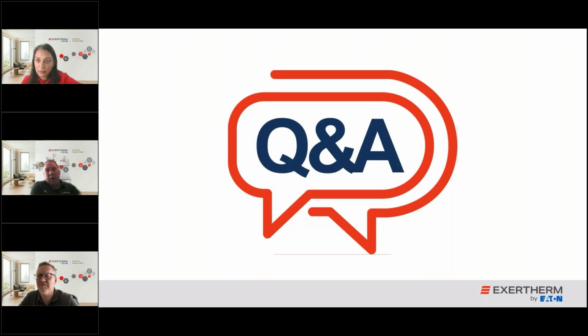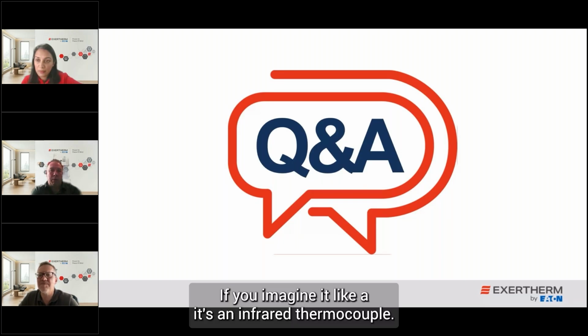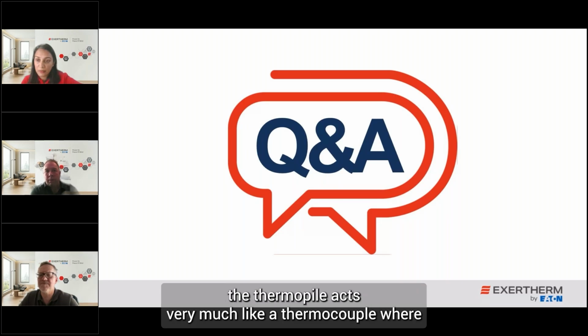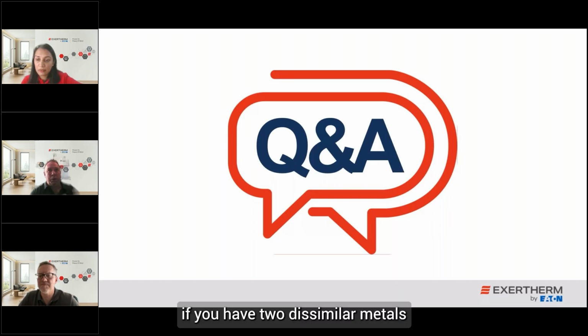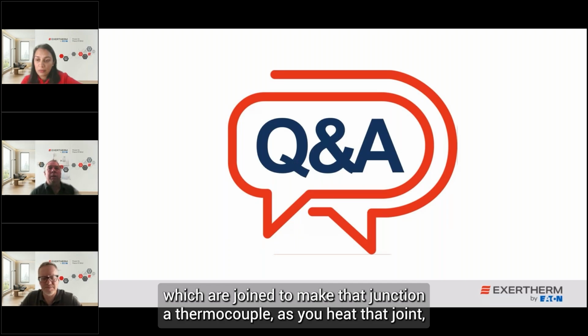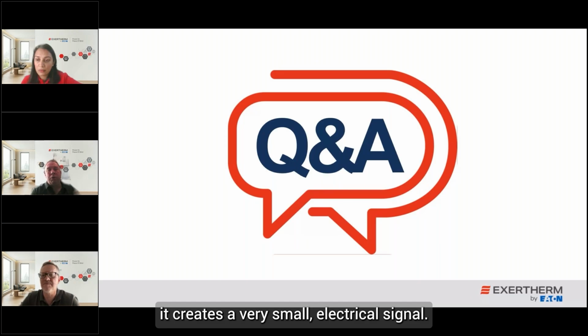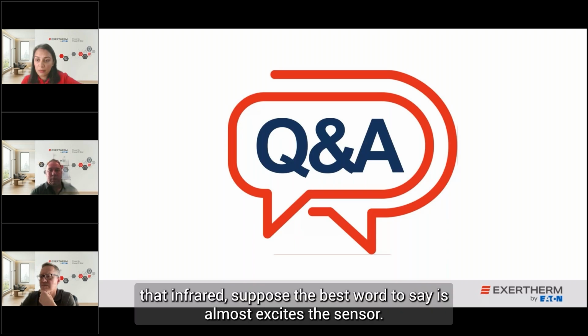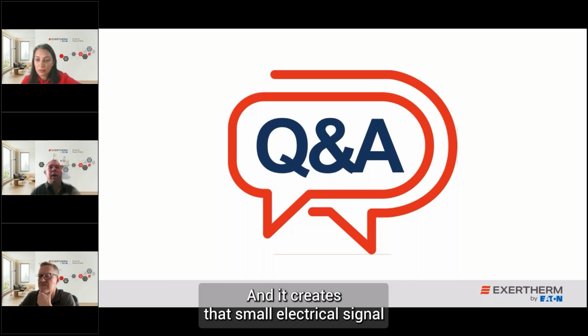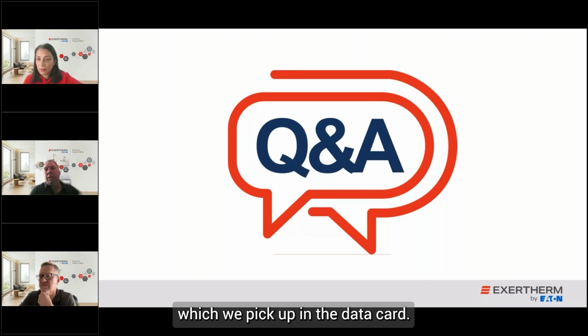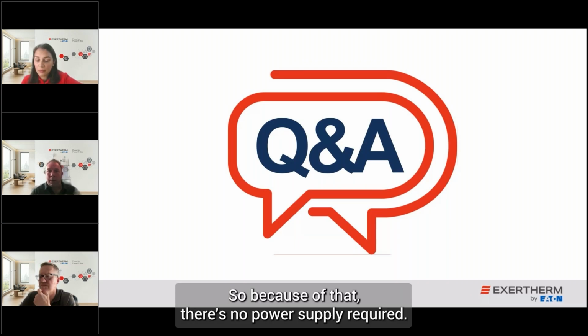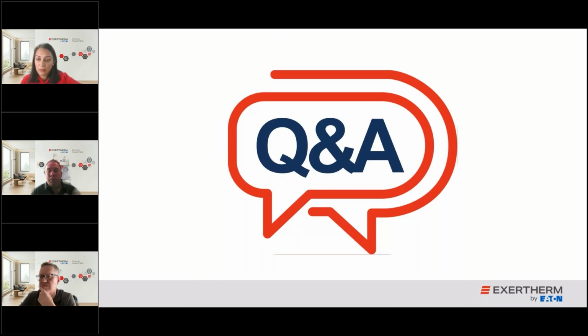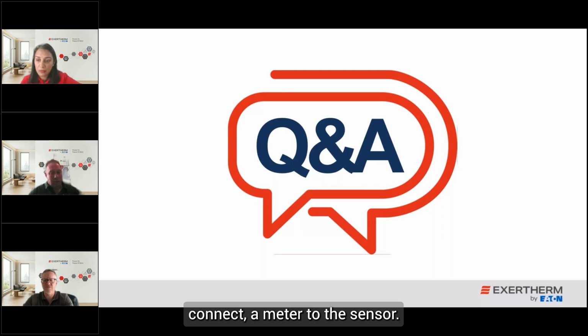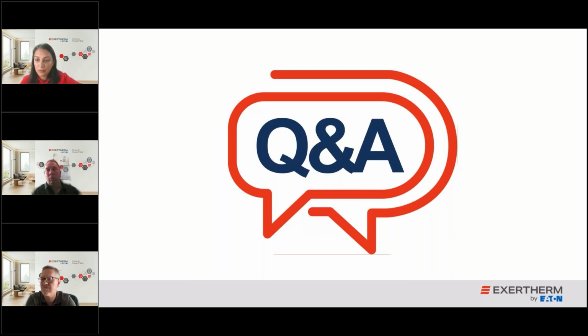The Exertherm sensor, if you imagine it like an infrared thermocouple - the thermopile in the sensor acts very much like a thermocouple, where if you have two dissimilar metals joined to make that junction, as you heat the joint it creates a very small electrical signal. A thermopile operates the same way: as it detects infrared, that infrared excites the sensor and creates a small electrical signal which we pick up in the data card. Because of that, there's no power supply required - it's not a current loop, doesn't need anything. You could actually connect a meter to the sensor, and if you put a hot target in front of it, you'll see that meter fluctuate.